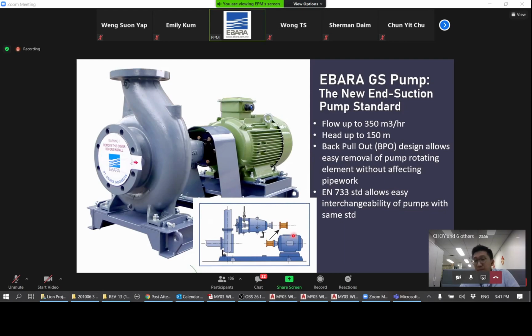And not only that, but it is designed to what we call an international standard EN733, which allows any pumps that are conforming to this standard to be replaced easily. So that means if you have another pump that has this same standard EN733, then you can just take out that pump and replace it with this pump, and the pipe and the connections will all fit properly. So that's what we call interchangeability of pumps. So these are some of the good features of this 100-year-old pump, which has been renewed.